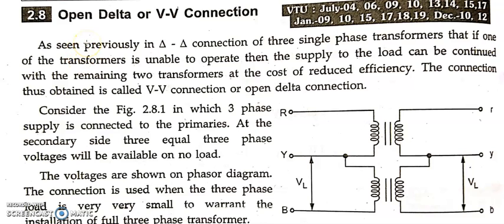Hello guys, in today's class we shall discuss open delta or VV connection. Like we have seen in the previous class, in a single three-phase transformer, if one of the windings fails, then the whole transformer has to be taken out of service. There you may have power interruption, so reliability is not that good. Again, the winding has to be replaced and put back into service, so it takes time.